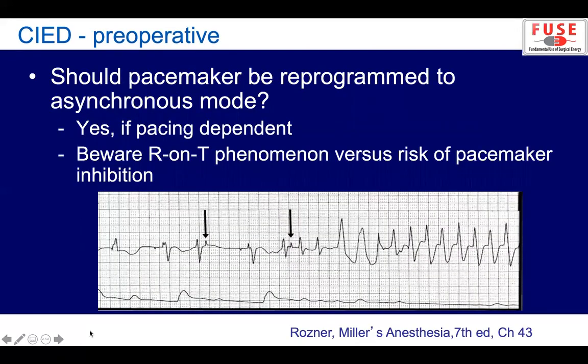The other question that always comes up is, should the pacemaker be reprogrammed to an asynchronous mode, right? So a DOO or a VOO mode. Most of the time, if the patient is pacemaker dependent and you're doing a procedure with a device that puts the patient at risk for interference, you probably want to reprogram that device. You do have to beware of the potential for the R-on-T phenomenon, where the pacemaker delivers an energy stimulus on top of a T wave, causing a ventricular tachycardia.